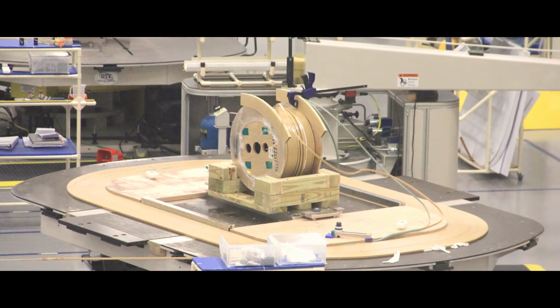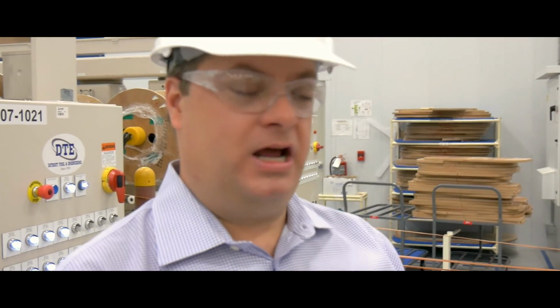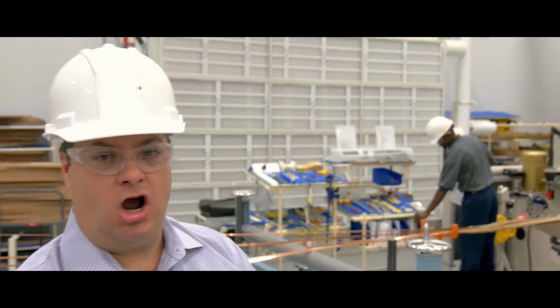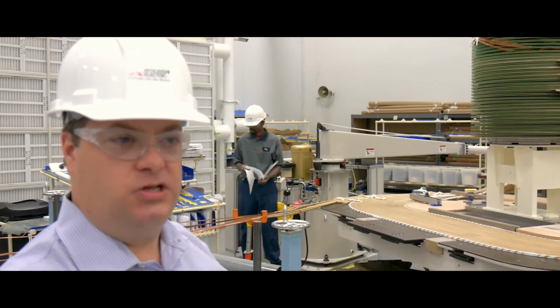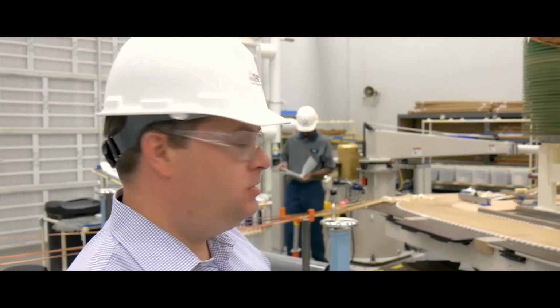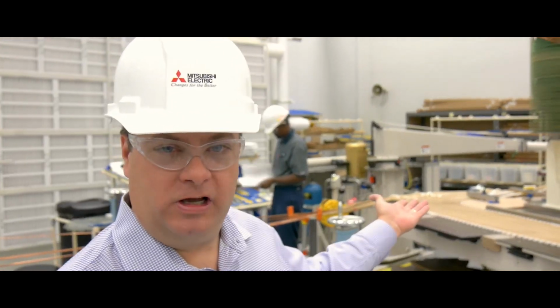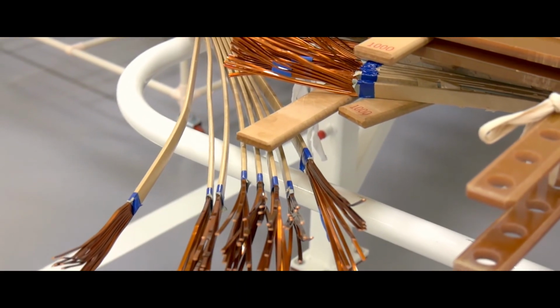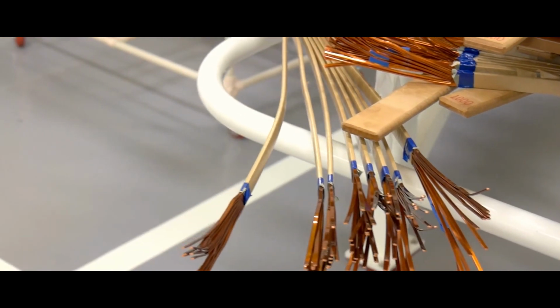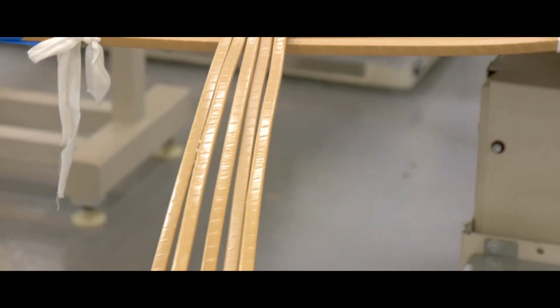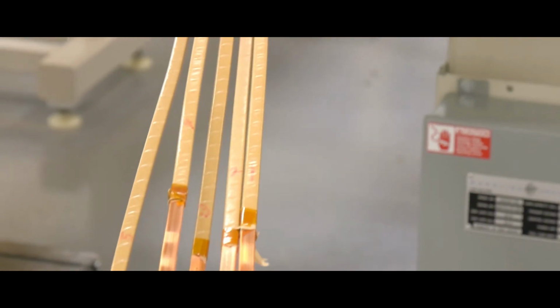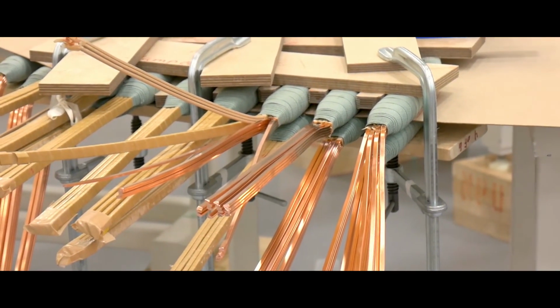If we look at the winding table, you can see the unique geometry of the coils we manufacture. This is specific for very high voltage, high power, large current applications, where this geometry has several advantages: a very large surface area that gives us very good coil-to-coil capacitance. This is a tap coil we're looking at, with multiple connections used to change the voltage during operation of the transformer by selecting different voltage taps in the winding.